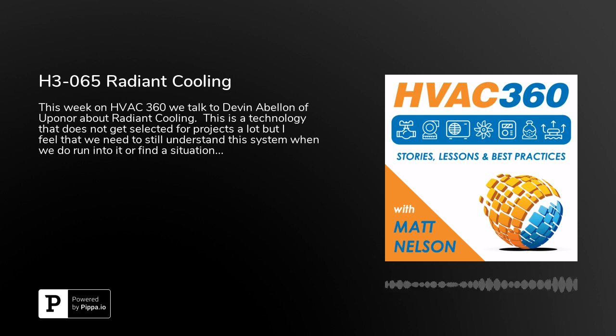The other thing to note, one of the key things with radiant cooling versus radiant heating, is that you do have to be aware of dew point so we can make sure that we avoid condensation. Obviously, moisture is the big gorilla in the room that people need to address, and no one ever brings that up. So let's talk about moisture in the air. Can you give us a back-to-basics overview of moisture?